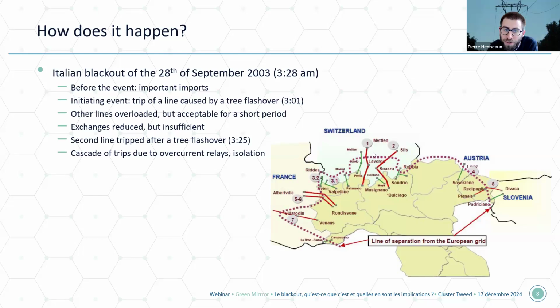And so you see that after 24 minutes, a second line tripped, the line number 2 in red. So again, extra high voltage, 380 kilovolt. And following that, because now we had two successive contingencies, the operator did not have time to significantly reduce the power exchanges and to put the system in N-1 security. Then the remaining lines were strongly overloaded and were disconnected quickly. And so in a few minutes afterwards, all the lines, so you see 3.1, 3.2, 4, 5, 6, 7, 8, and so on, all lines between Italy and continental Europe were disconnected due to overcurrent relays. That led to the isolation of Italy.